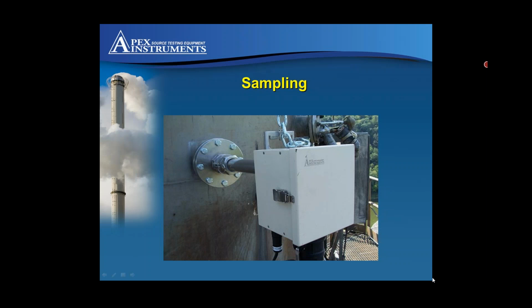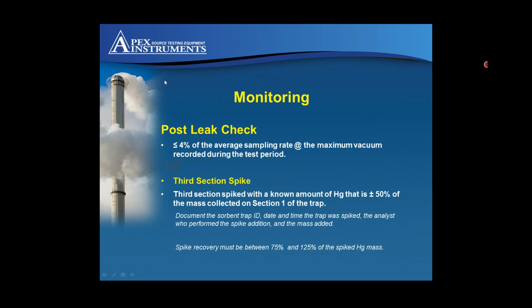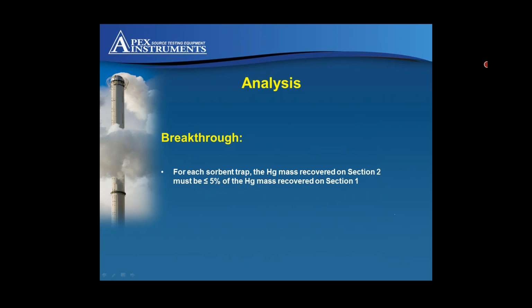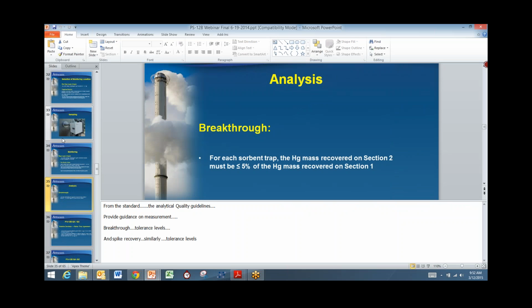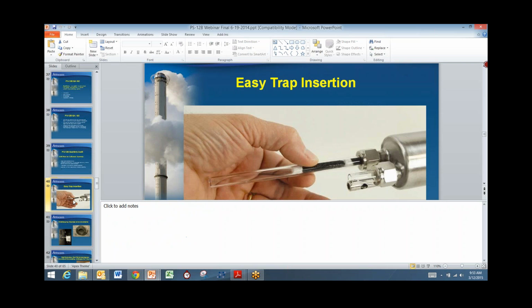What consumables would we need to service the probe? The probe itself, the only thing you need is where the traps go into the probe. There's some small glass-filled ferrules, and that's what actually makes the leak-tight seal. They need to be replaced periodically, monthly, every 2 months. They're just small little 10-millimeter ferrules. You can't see it, it basically sits right behind that nut.